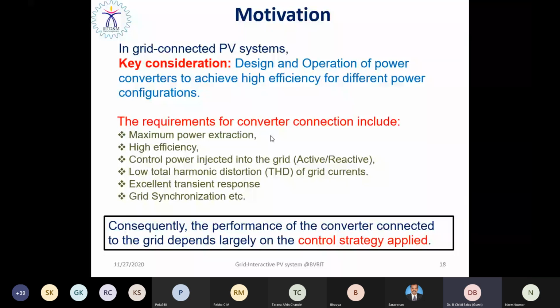It should have an excellent transient response. As we use the power electronics converter, it has to improve the dynamics of the entire system, so that any abnormal or unbalanced load connected at the point of common coupling is handled, and it has to ensure an excellent transient response even during fault conditions. And moreover, it has to have good synchronization.